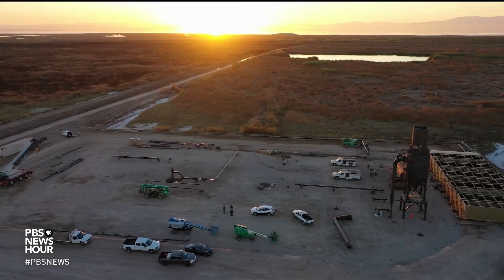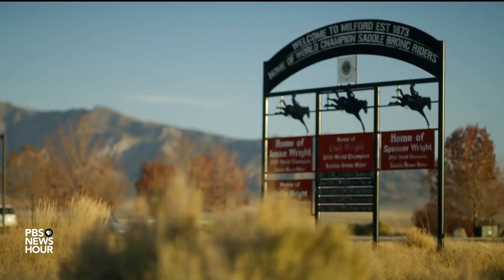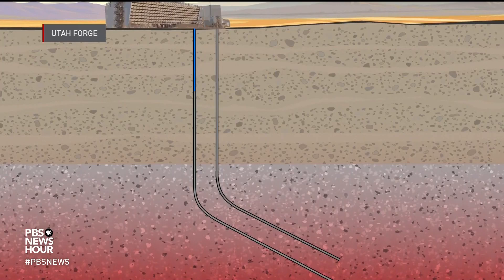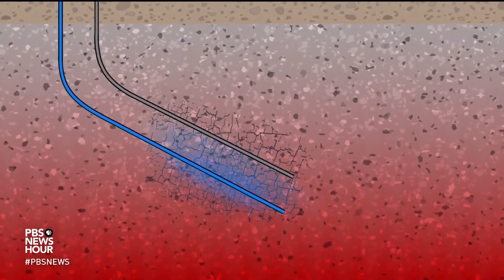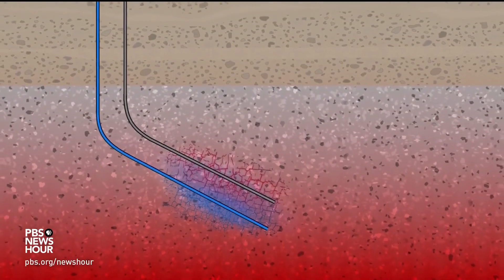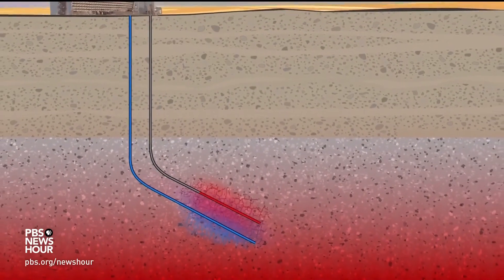The types of resources that you need to produce power are not available everywhere within drillable depths. It's just at this stage not economic to produce steam from extremely deep wells. But that could be changing at the FORGE project in Utah. Here, the Department of Energy is piloting a technique called enhanced geothermal systems, or EGS. The plan is to drill two deep wells into low-permeable hot rock, fracture the rock in between the wells to create a reservoir, and then pump water into the cracks. It returns to the surface piping hot.